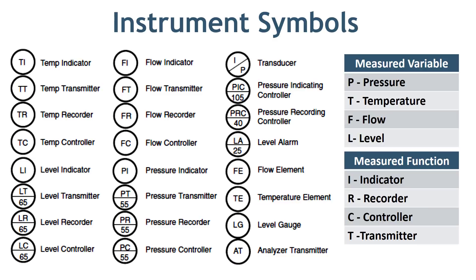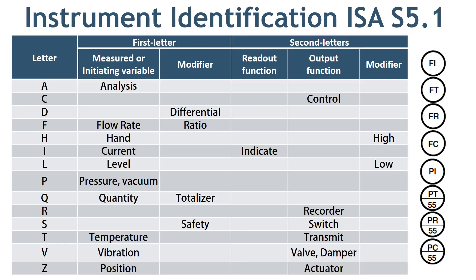Now back to our symbols. Here you can see the various instrument bubbles. In a process plant, more than 90% of instruments measure either pressure, temperature, flow, or level. You can see the small table on the right-hand side which shows the first letter of the instrument. The functions of these instruments are either to indicate, record, control, or transmit the measured value. On this table, you can see the meaning of the first letter and subsequent letters — you can pause the video to read all the letters and their meanings.